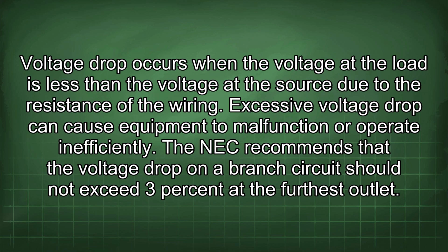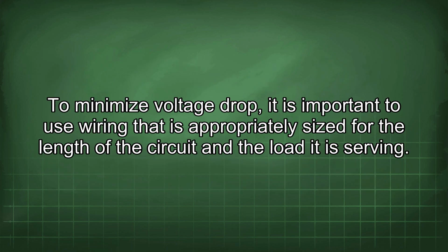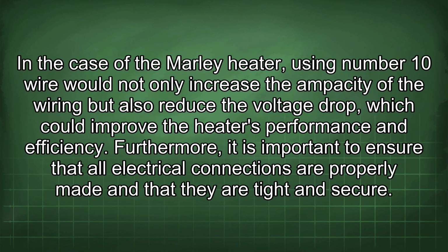The NEC recommends that the voltage drop on the branch circuit should not exceed 3% at the furthest outlet. To minimize voltage drop, it is important to use wiring that is appropriately sized for the length of the circuit and the load it is serving. In the case of the Marley heater, using number 10 wire would not only increase the ampacity of the wiring but also reduce the voltage drop, which could improve the heater's performance and efficiency.